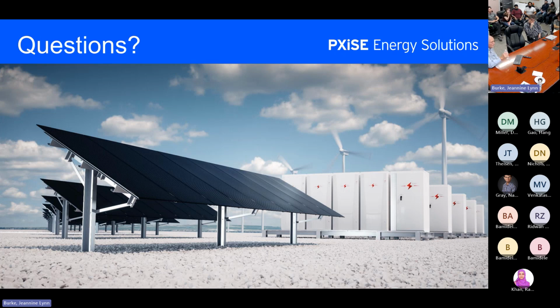Yeah, so you had a question. Yeah, I actually have 2 questions. The first one is a very short one. You mentioned that right now you are pushing the narrative for the inverters to always be in grid forming mode, and when the DG comes up, it has to be following the voltage. I'm kind of confused as to how that is possible, because the conventional way is that the DG is always the grid forming, while even if you have grid forming inverters, once the DG is there, they have to just follow the voltage and frequency of the DG. So how do we do the opposite? That's the first question. And the second one is kind of a very long one.